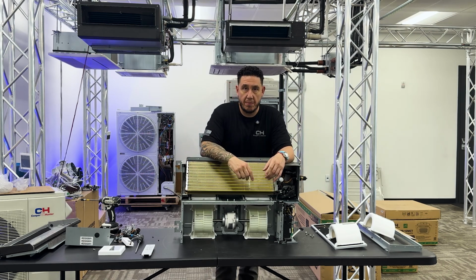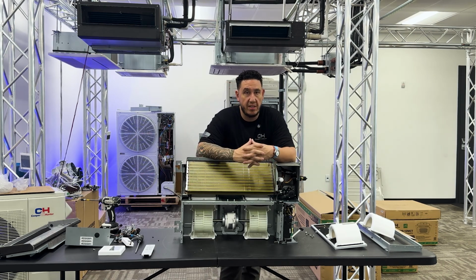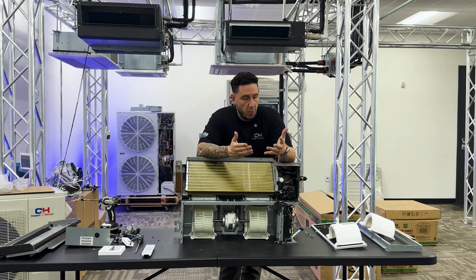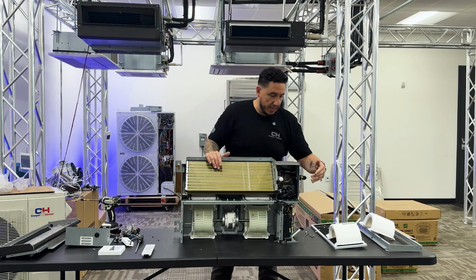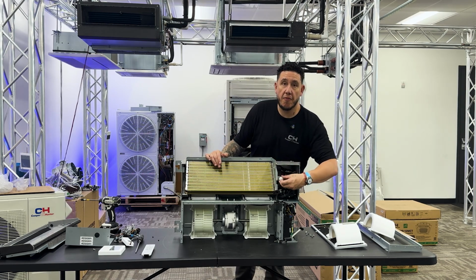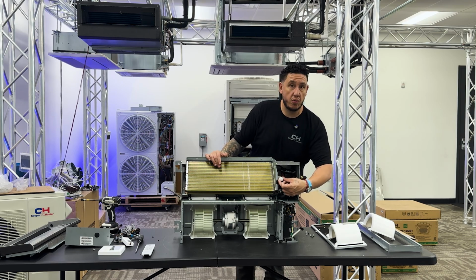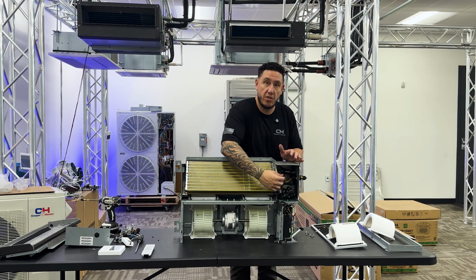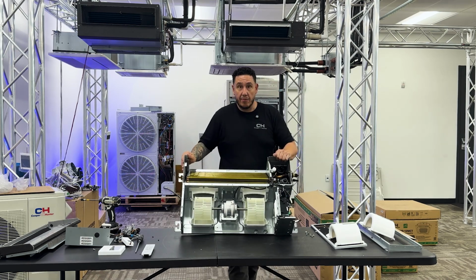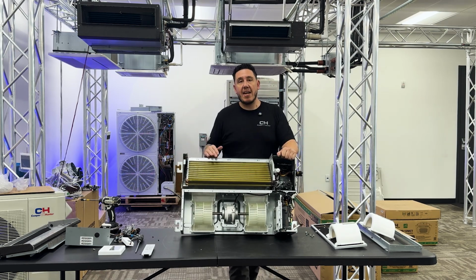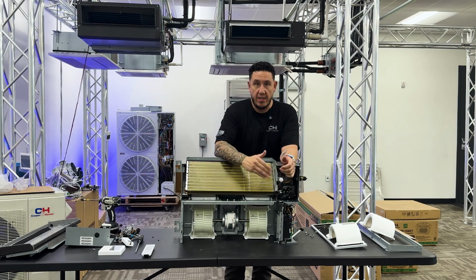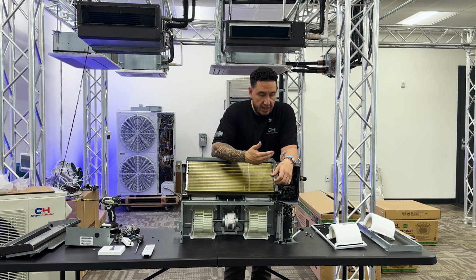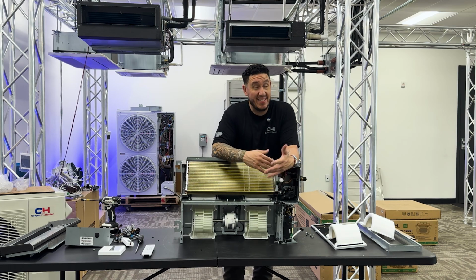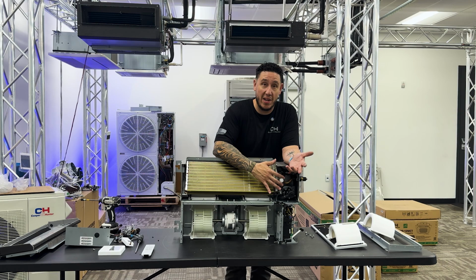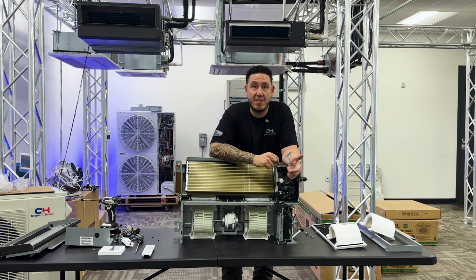So earlier we talked about making sure that this is in the correct position when it comes to installation. Common question we get, Ed, what happens if this is installed upside down? What's gonna occur? Remember, this does come with a condensation pump built right in, as you could see. And right up front, this is our emergency float switch. It's exactly what it's called, a float switch. If this is flat upside down, you notice how that switch just fell back? Now it's deactivating the system, and I'm getting an EE error code saying failed condensation, letting me know that this unit is dead on startup. It's not in fact dead, it's installed upside down. That's why this switch is activating. So that's letting me know that this is in the incorrect position.